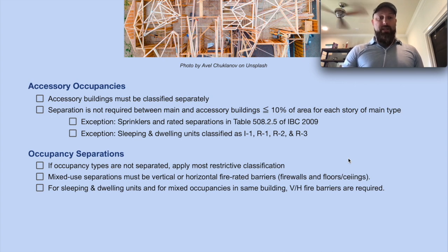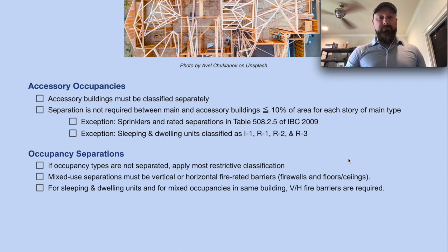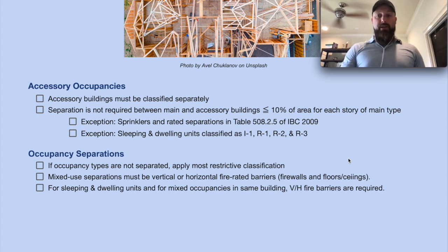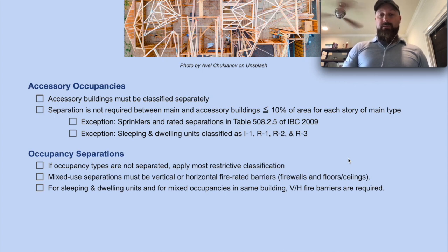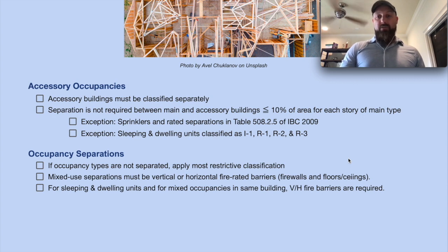The final section for this page is occupancy separations. If the occupancy types are not separated, we must apply the most restrictive classification. Mixed use separations must be vertical or horizontal fire-rated barriers. These are also called firewalls, and horizontal assemblies are our floors and ceilings that are fire rated. For sleeping and dwelling units and for mixed occupancies in the same building, vertical and/or horizontal fire barriers are required.